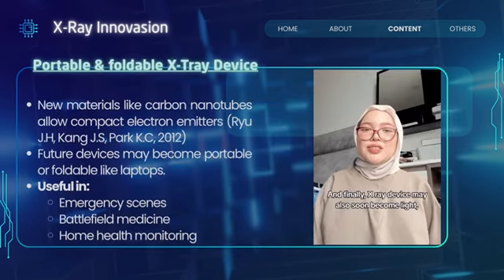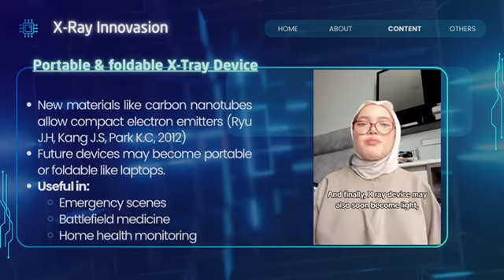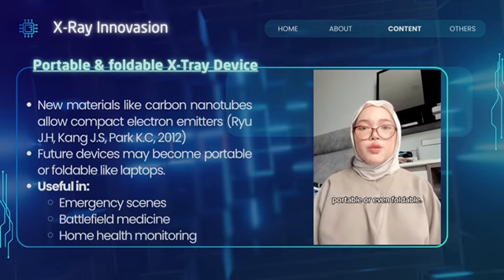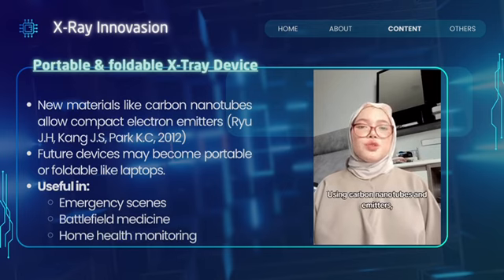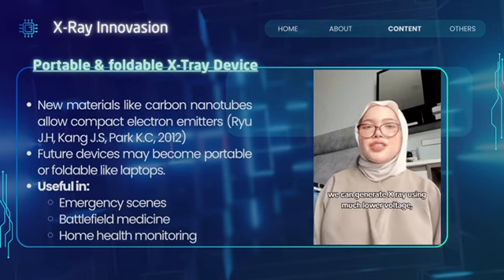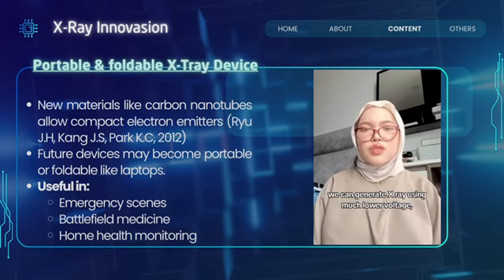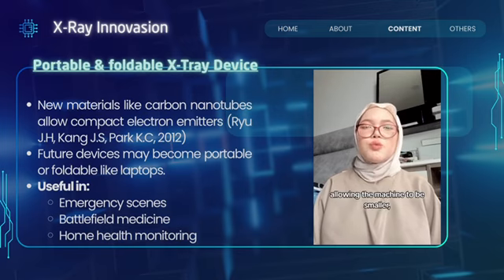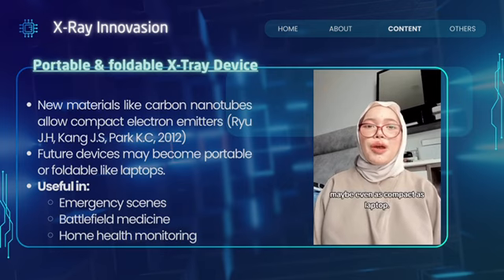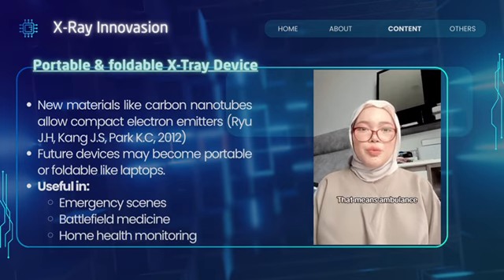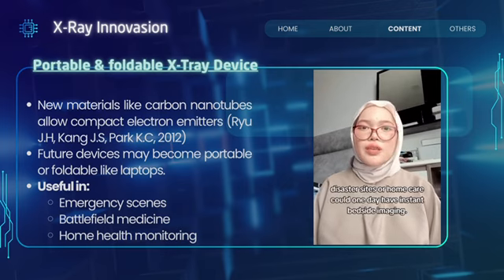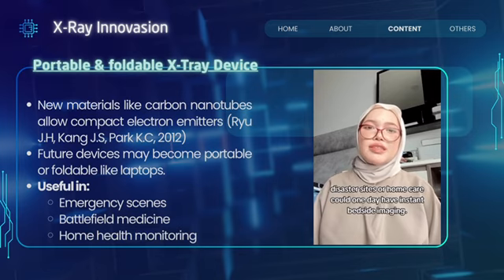And finally, X-ray devices may also soon become light, portable, or even foldable. Using carbon nanotube (CNT) emitters, we can generate X-rays using much lower voltage, allowing the machine to be smaller, maybe even as compact as a laptop. That means ambulances, disaster sites, or home care could one day have instant bedside imaging.